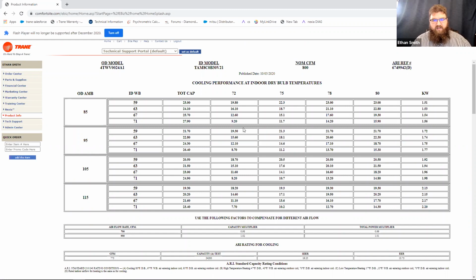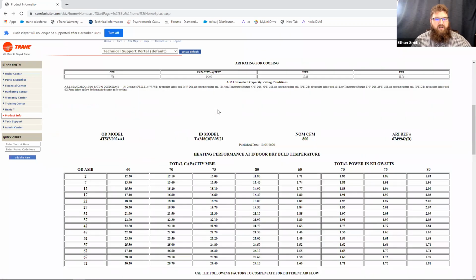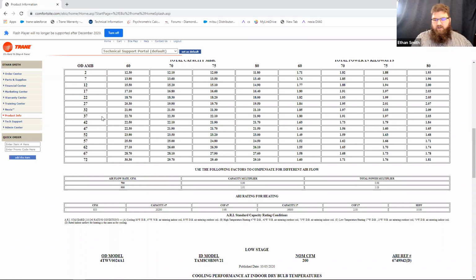And you can come down in here and see all those capacities are there as well. This is cooling. Come down here, we've got that same chart in heating. So if we were to do that formula again, let me grab a Post-it note here so I can do my math. We're going to come down to 37 degrees outdoor temperature. So there's my data line that I'm going to pay attention to, right there. We go to 70 degrees indoor. My total BTU output for that unit is going to be 22,300 BTUs per hour. Okay, I need the wattage that I'm going to consume to do that as well. So I'm going to come over here to my 70-degree indoor temperature, and I get 1.9 kilowatts. So that's 1,910 watts, excuse me, times that by 3.41. Let me do some math on my end. So grab my calculator.